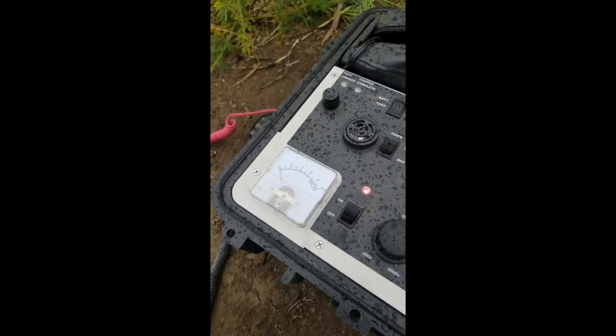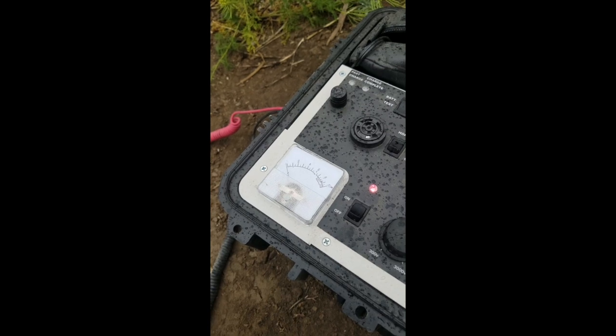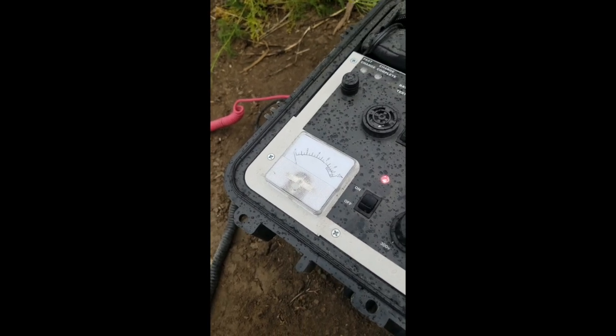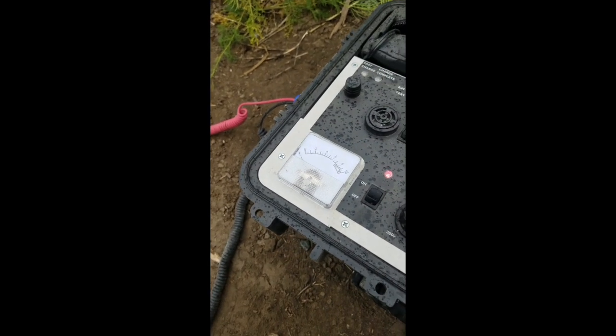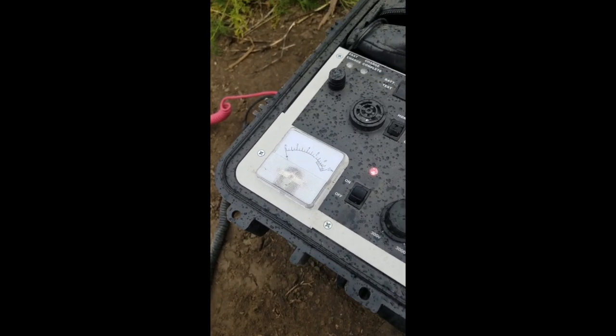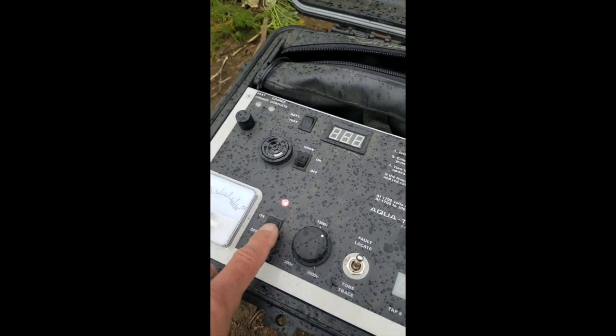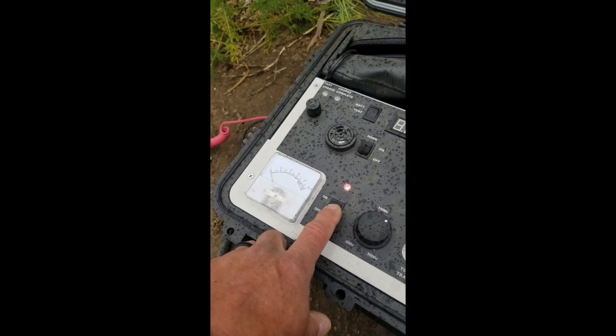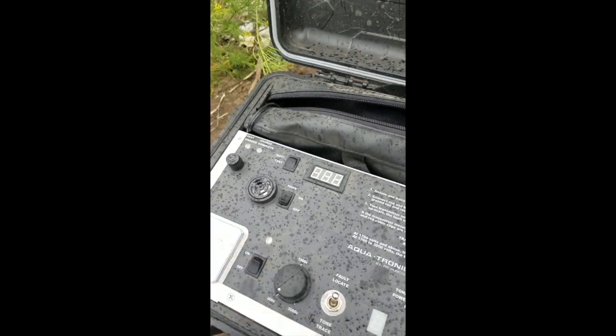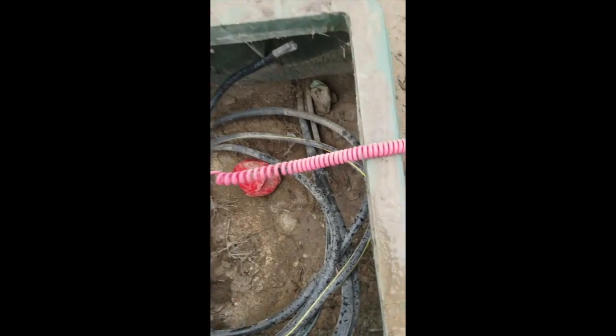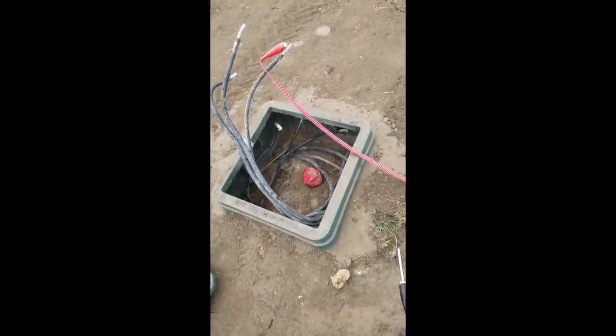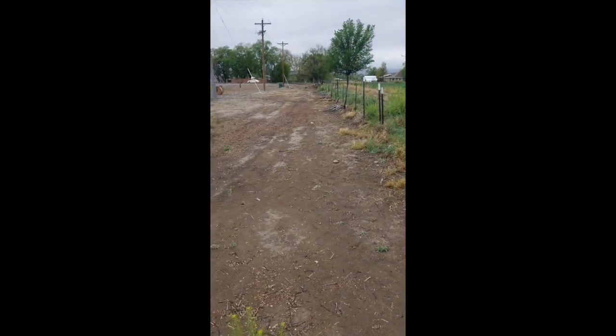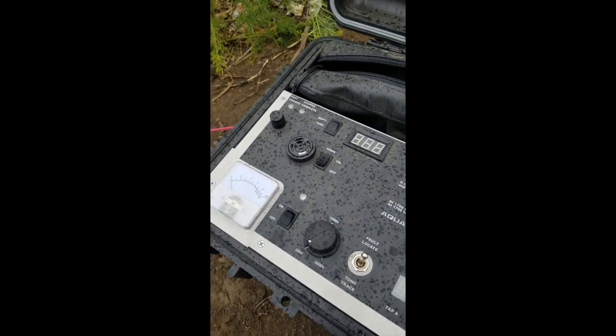The pulse is going down the cable, reflecting off the end and coming back in through the positive output wire, making the needle go negative. So that cable is ready to be put back in service. I'm just going to throw the connection over here to another leg, going a different direction down to that end over there. I don't know if you can see the box down there, but 150 feet or so.